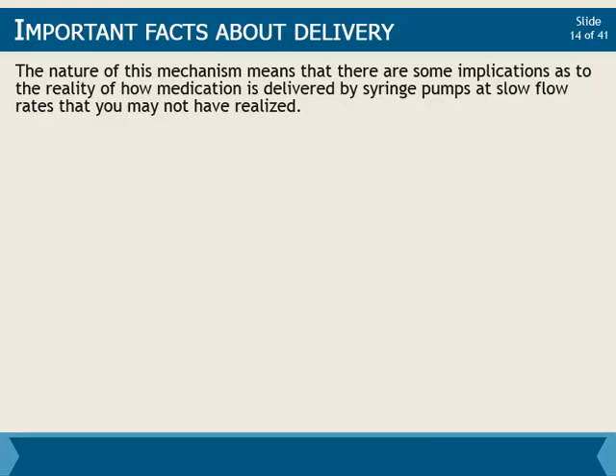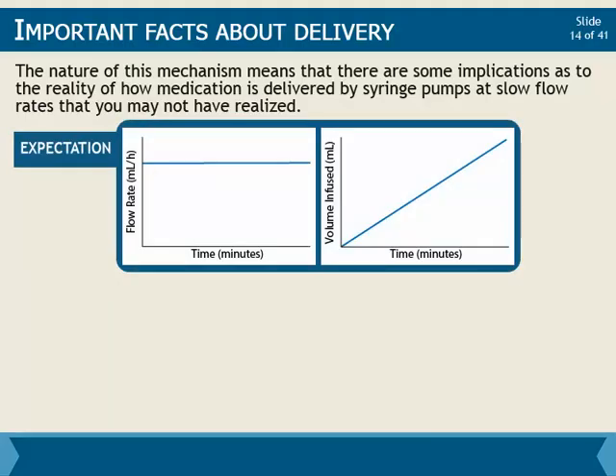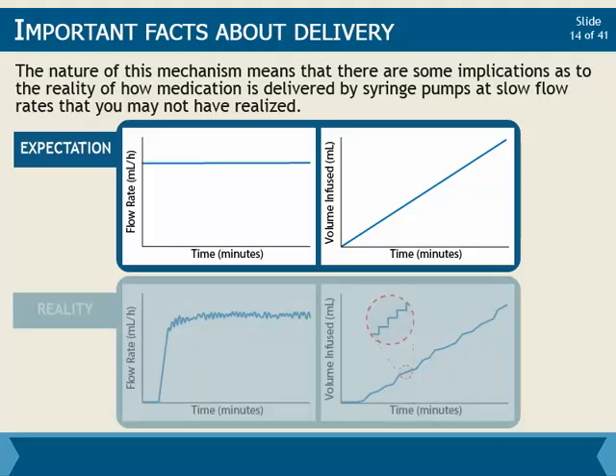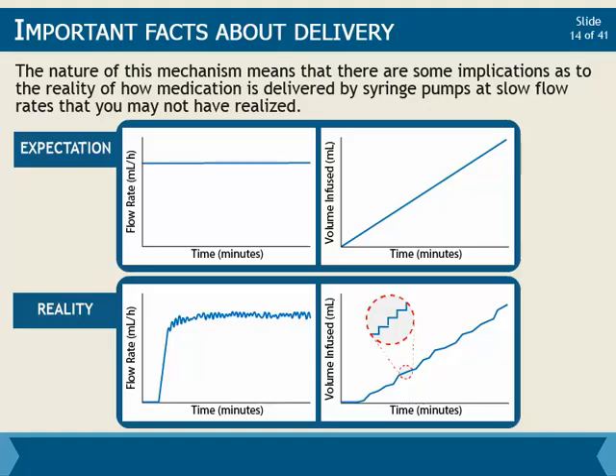The nature of this mechanism means that there are some implications as to the reality of how medication is delivered by syringe pumps at slow flow rates that you may not have realized. When you program a flow rate, you may expect the pump to instantly and continuously deliver at this flow rate for the duration of the infusion. In turn, you may expect the volume infused to the patient to steadily increase at a consistent rate. However, this is not the reality of the situation, and the flow rate and volume infused may look a bit more like the images now shown. We will discuss why this is in the sections ahead.